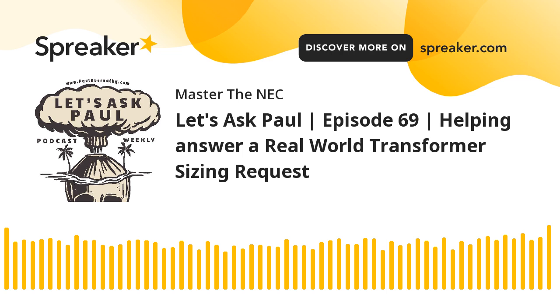The only other comment I'll make is the 330 feet. Just don't forget about voltage drop. I know it's not in the code, but it's a prudent design. You want to make sure this equipment runs efficiently, and you don't want to be called back because stuff gets burning up because of excessive length. So you might end up putting larger conductors in anyway than what's going to be based on our calculation today. But I just want you to keep all that stuff rattling around in your brain as you do that.